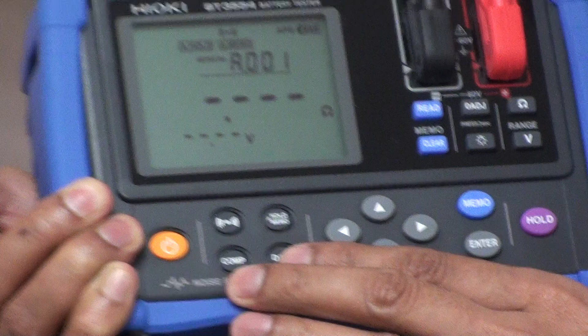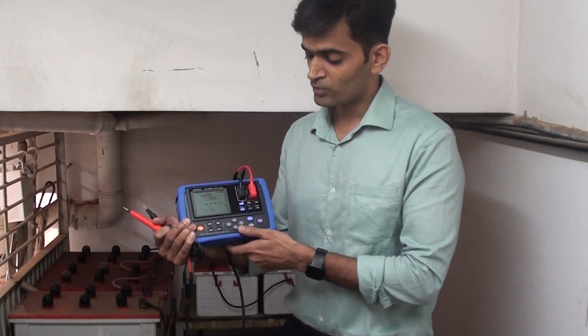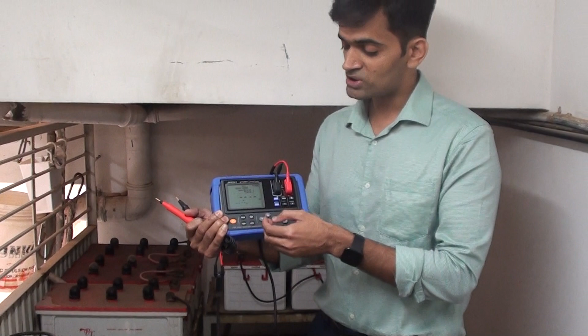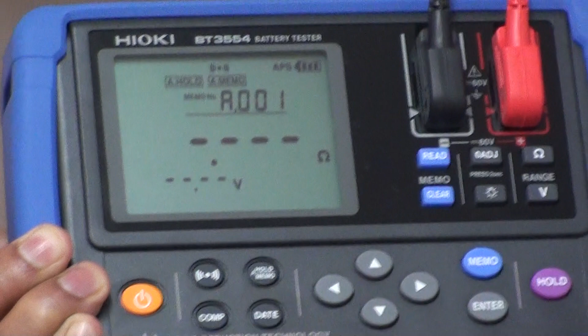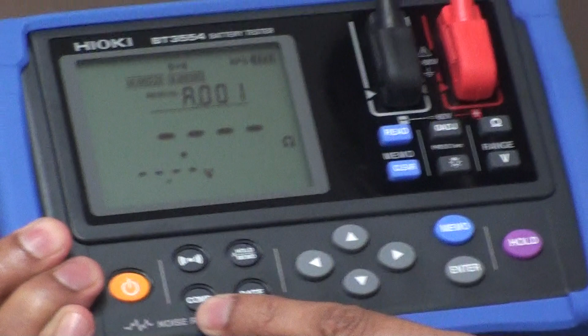And the advantage of this instrument, there is a comparator method in this. Once you switch on the comparator method, you set the resistance and voltage range, like lower and upper limits. So while doing the testing, you do not need to check pass or fail. Once you set this comparator, it will automatically show on the display and beep an alarm if you are crossing the voltage or resistance range above the setting. So this is the advantage of the comparator method.